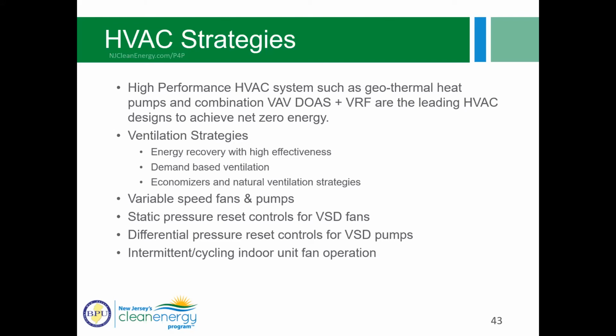And those evaporators tend to have really low fan power. And they cycle during occupied hours, they just cycle on and off with the heating and cooling loads. And then to meet the outside air requirements, you'd have your variable air volume, direct outside air unit decoupled from that evaporator, providing that outside air. And you would do that using demand controlled ventilation to reduce outside air levels when occupant density is reduced. So that's found to be a very high performing strategy.